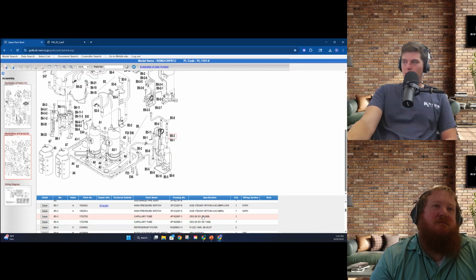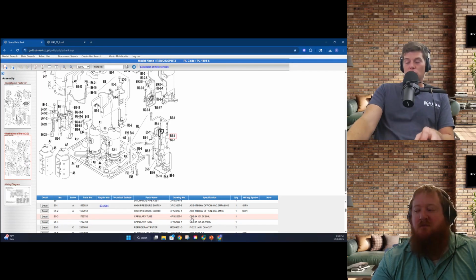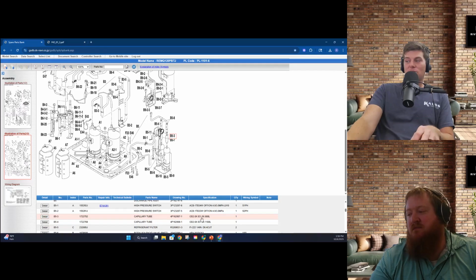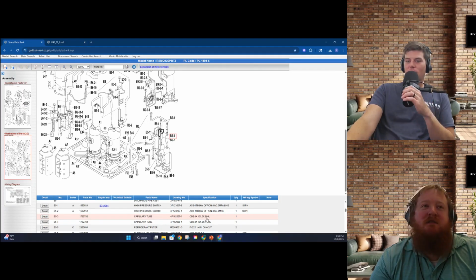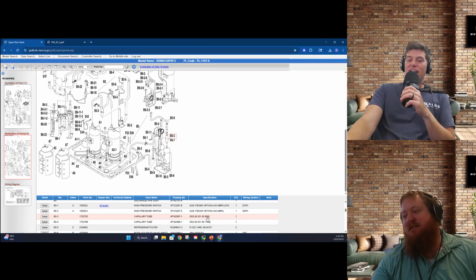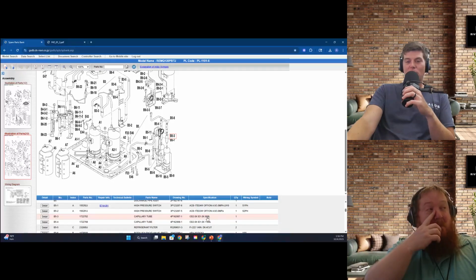Yes. No, 100%. But if we go here to the cap tube section, and I love this on VRV3, so on VRV4, we got to go old school on that one. Look at VRV3. They're two different sizes. And then the two different sizes here, we can break this down. If we go down to the specification naming section, you'll see here OD is 2.0 times ID 1.0 times 880L. So the OD is 2 millimeters, the ID is 1 millimeter, and the last thing is 880. It's the actual millimeters long.